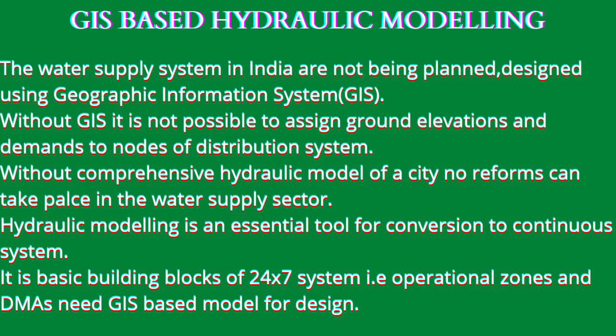For the design aspect of a 24x7 water supply system, the basic tool required is GIS-based hydraulic modeling. Previously, schemes were not designed based on territorial, need-based, geographical, or topographical considerations. The guidelines now recommend following GIS-based hydraulic modeling before designing these schemes. It is observed that water supply systems in India are not being planned and designed using Geographic Information Systems, GIS. Without GIS, it is not possible to assign ground elevations and demands to the large number of nodes in a distribution system. The Ministry has published an advisory on GIS mapping of water supply and sewerage infrastructure, which may be referred to for the same.